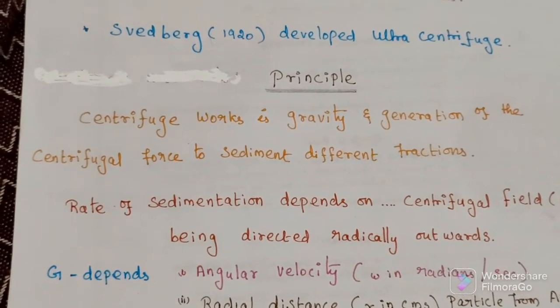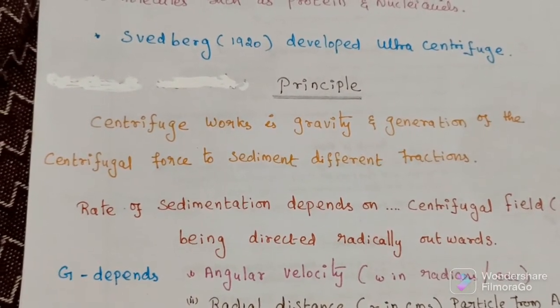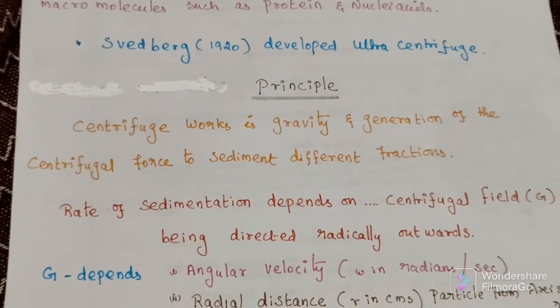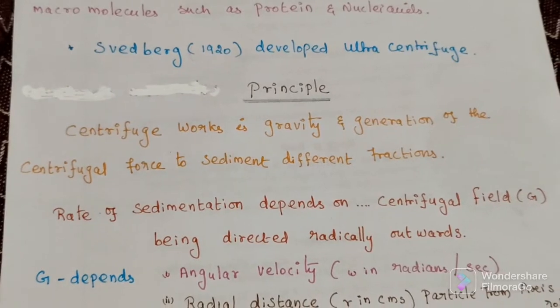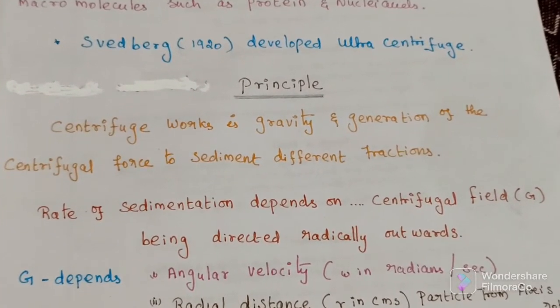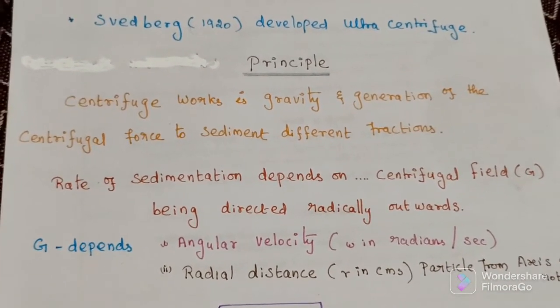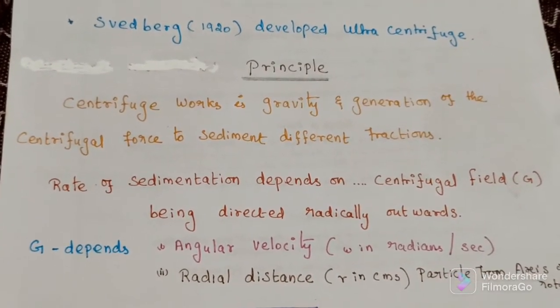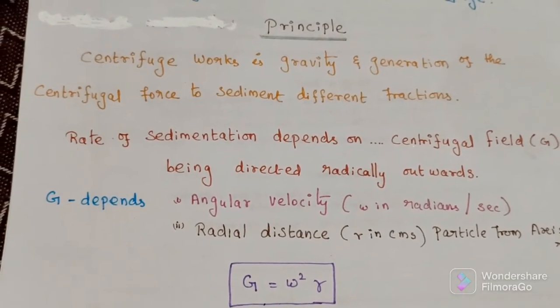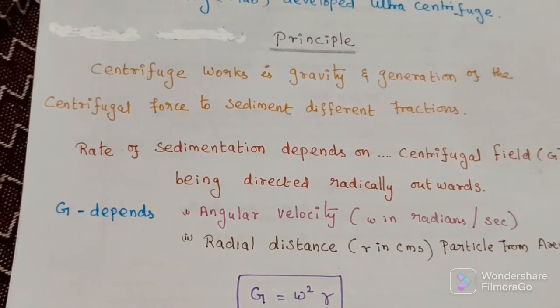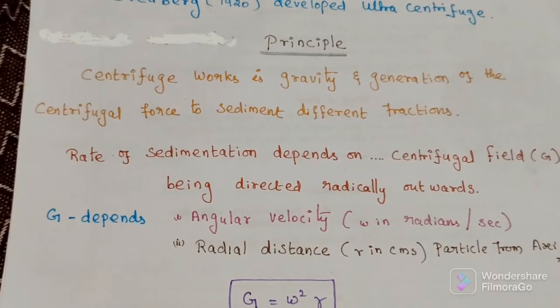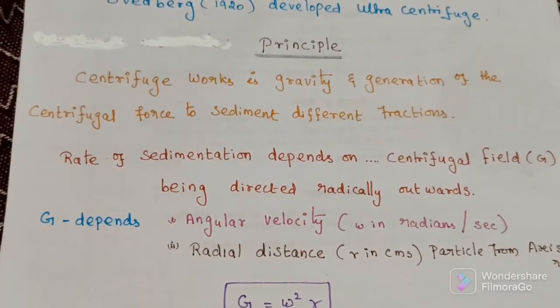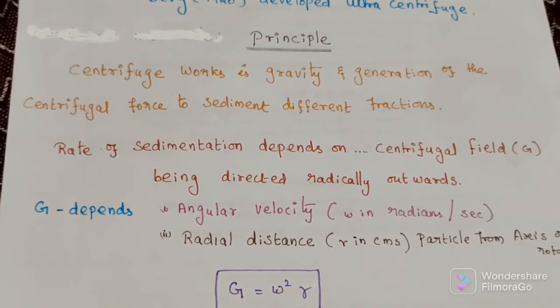What is the principle? The basic physics on which the centrifuge works is gravity and the generation of centrifugal force to sediment different types of fractions. The rate of sedimentation depends on the applied centrifugal field, that is G. G depends on angular velocity omega in radians per second and radial distance R in cm. So G represents the centrifugal force, omega is angular velocity, and R is the radial distance.